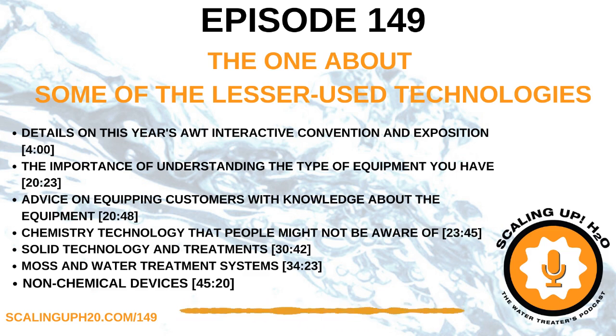Now, those are full ported, and they're going to open up, and you get a full stream that's utilized for blowdown, so you don't have to worry about those things plugging up. These capacitor-driven valves have been out for 6 or 8 years now, I may be wrong there, but they're great little valves. I've used them in lots of applications. I've had a few fail, but if your controller tells you that you've got water flowing and it shouldn't be, you can address that.